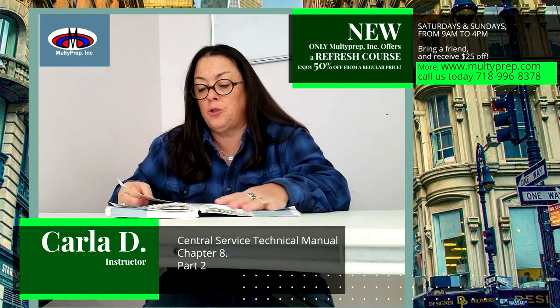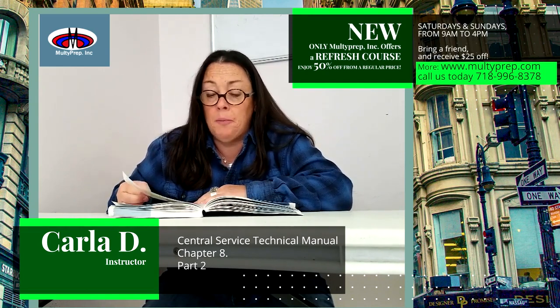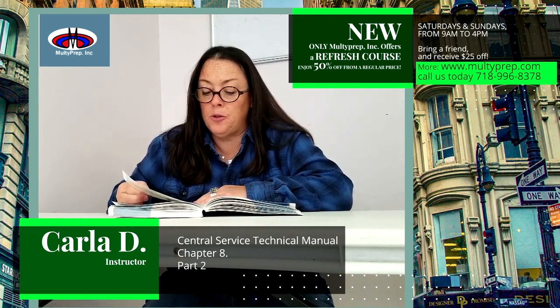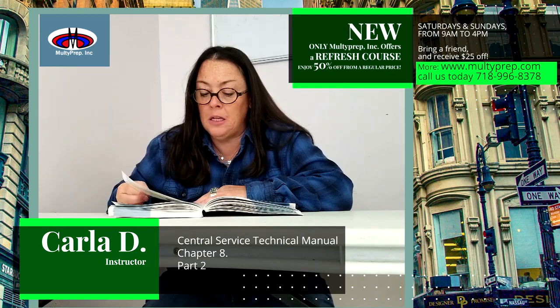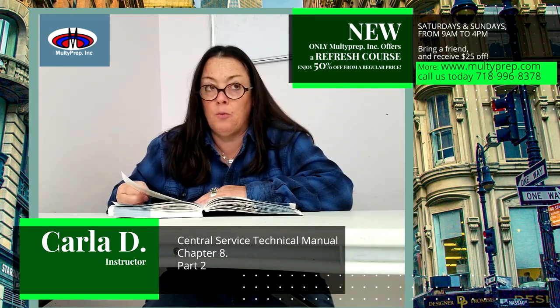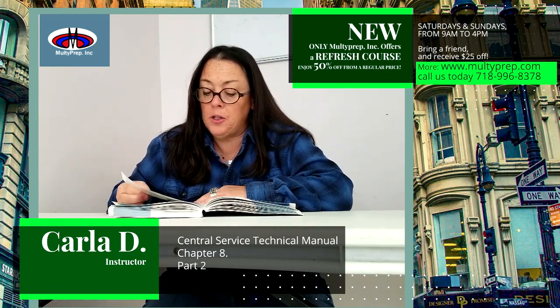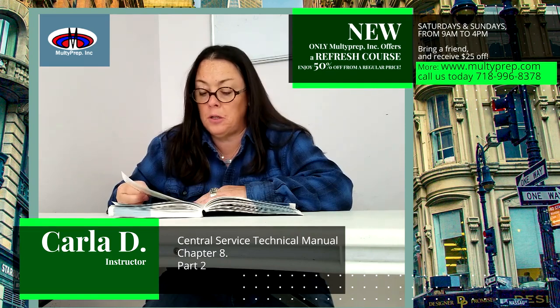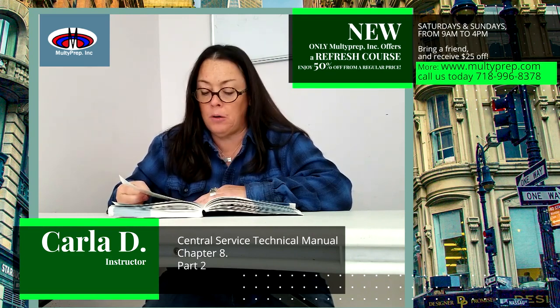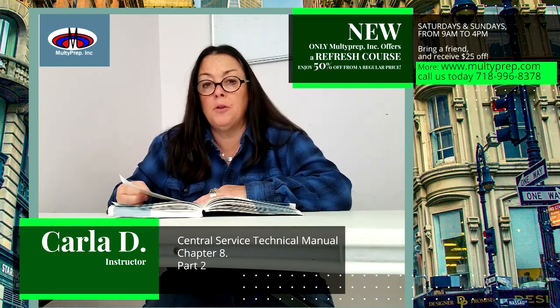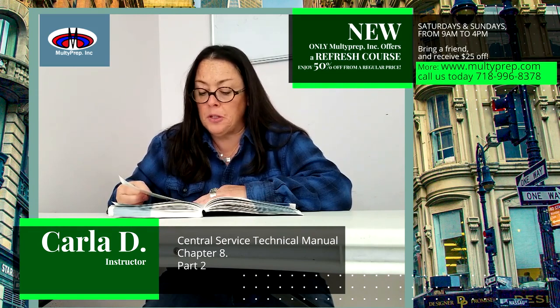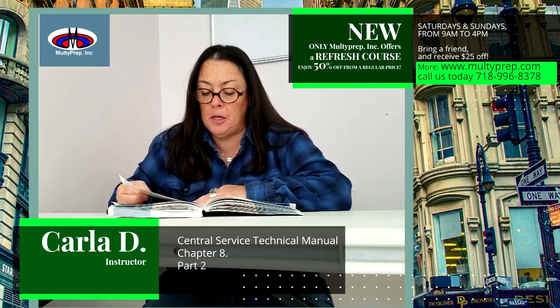Lubricants, often called instrument milk because of its milky appearance, are an important part of the instrument maintenance program because they help maintain the integrity of instruments and keep them in good working order. Lubrication is performed after cleaning as one of the final steps in the mechanical wash process, or it can be applied manually in the clean assembly area using a spray bottle. In the past, instrument baths, pans filled with instrument lubricating solution, were commonly used. This process has been discontinued because of increased risk of contamination.